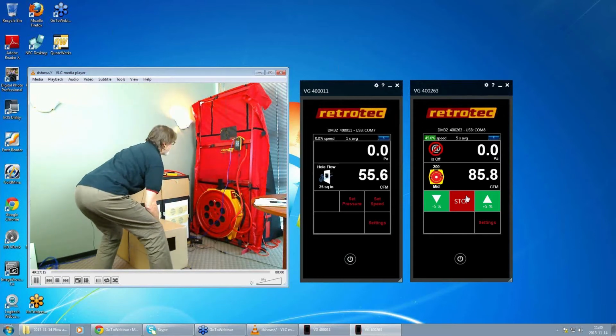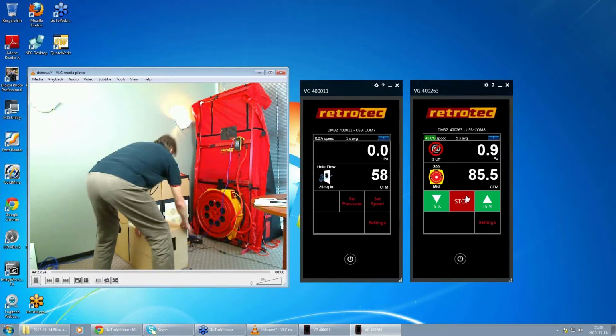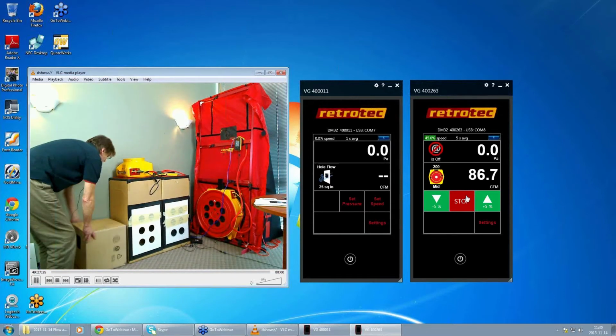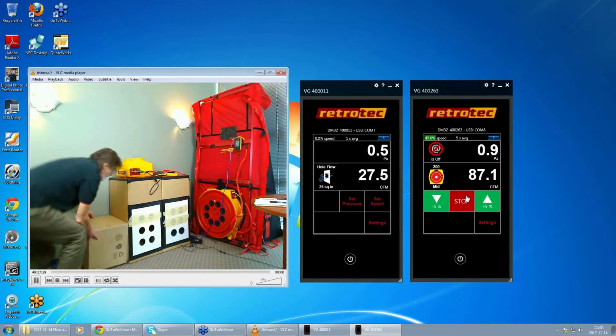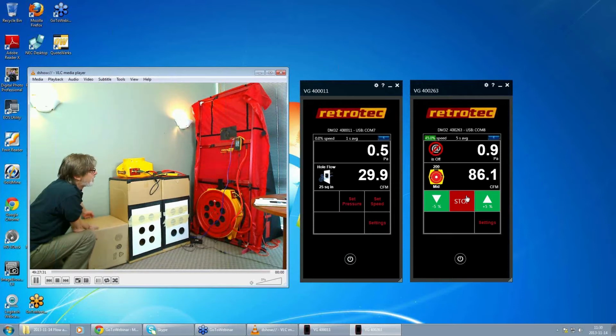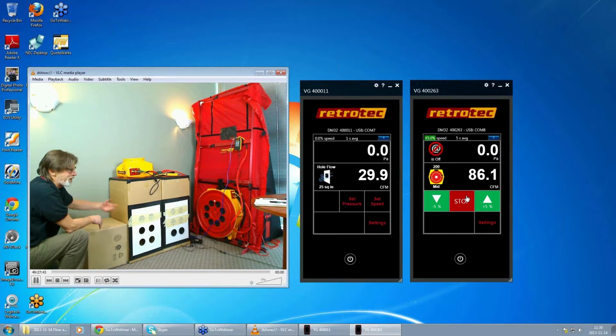Let's just take another look here. 58. 57 CFM through that one. Around 30, so 87 CFM in total. It's actually doing a pretty fair job. But recall how much of a problem we had when we had a supply flow. So an exhaust flow is going to work fine.